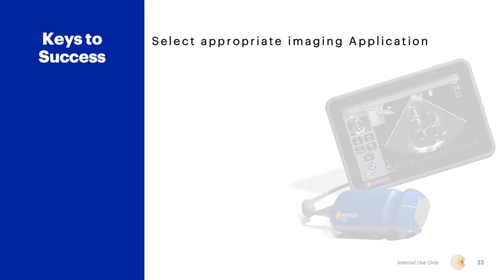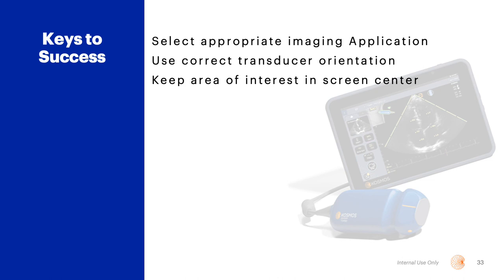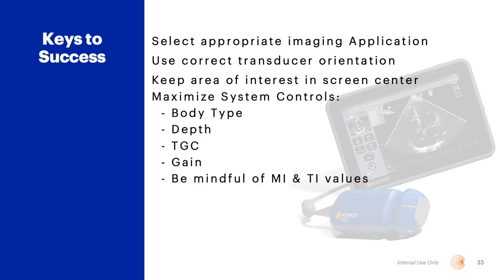Keys to success for ultrasound imaging include: selecting the appropriate imaging application, using the correct transducer orientation, keeping the area of interest in the screen center, and being certain to maximize the system controls — to include body type, depth, TGC, and gain — while being mindful of the MI and TI values.